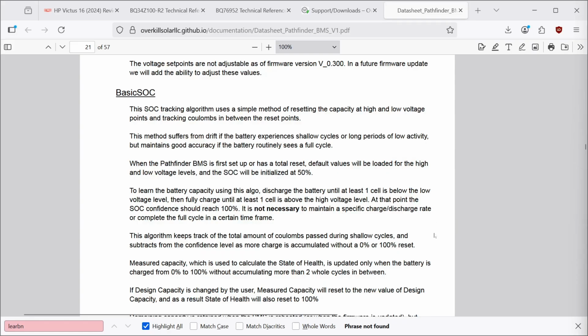You don't have to do this all at once. Every time the voltage level hits the high or low thresholds, the algorithm resets to either 0 or 100% as appropriate, and also updates the confidence level. If you've done a full cycle from 0 to 100%, the algorithm reports 100% confidence. The longer, or the more charge cycles it accumulates in between those high and low set points, the more the confidence level will drop over time until it actually gets a 0 or 100% reading by voltage.